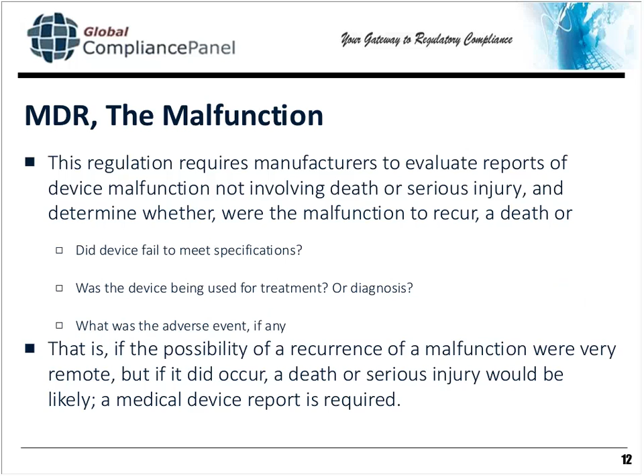If the source is a complaint, be sure that the complaint file has a record. Remember, did it fail to meet specs? Was it being used for treatment or diagnosis? Was it being used for the indication in the labeling? And what was the adverse event? And what was the relationship of the device to the event? Was there any? If there isn't any relationship, simply explain this conclusion. You don't really have to do an MDR at that point, but you do have to have your reasoning in your complaint file.